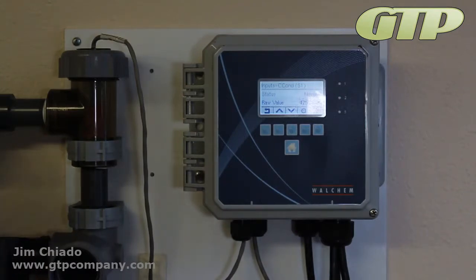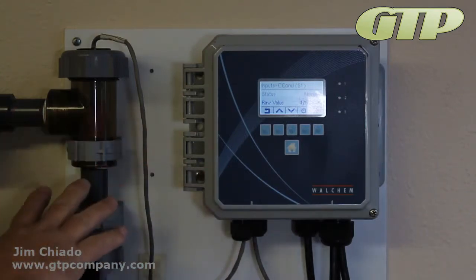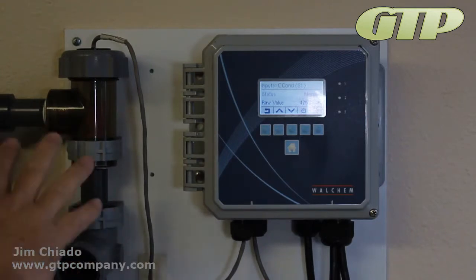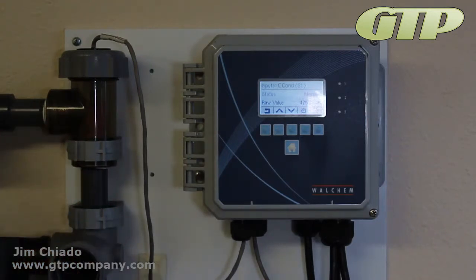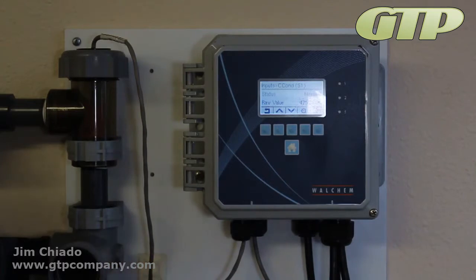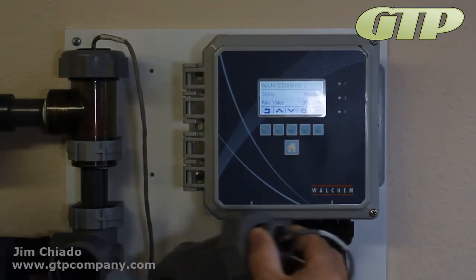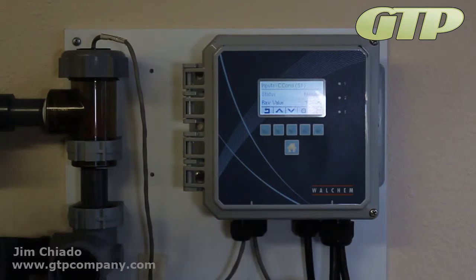If you pull it out and you can get it to do a calibration, but in the system it's out of range, there's some electrical interference or something going on in that system. You've isolated it from all those things. But if we put it on here and we're still getting out of range, this is what we're going to talk about. It's 1.5 times what it thinks the raw value is. This is just city water for me. I've got my little test tee, and I've got some 1400 microsiemens. You can see that the machine thinks it's about 1100.